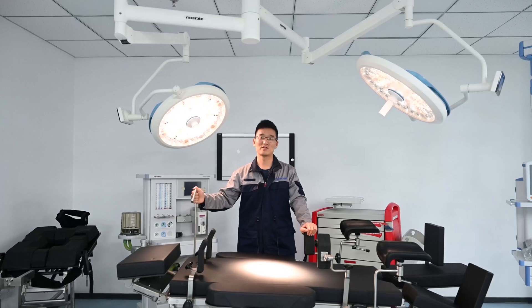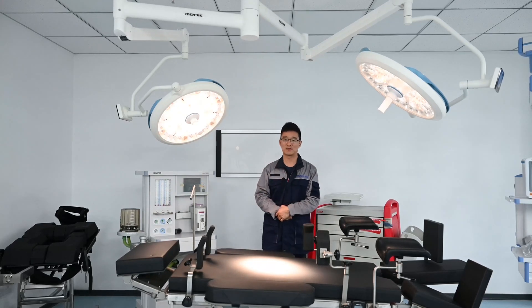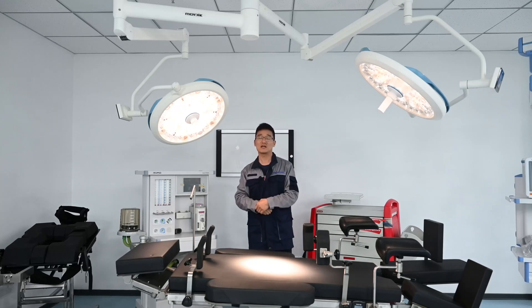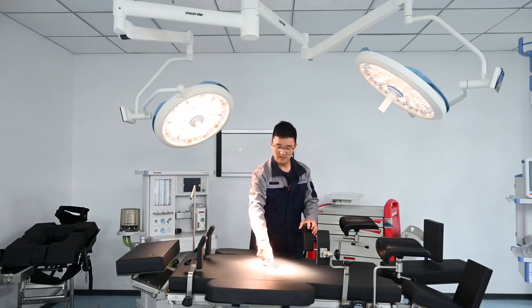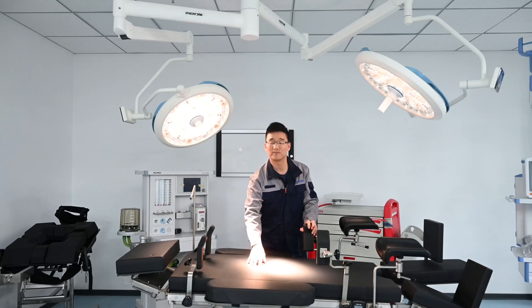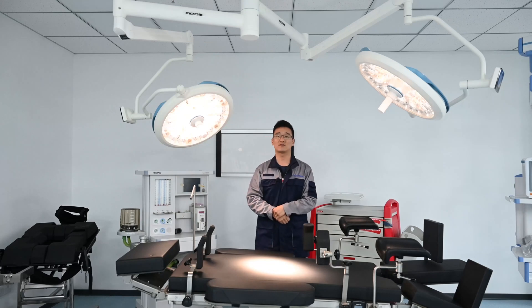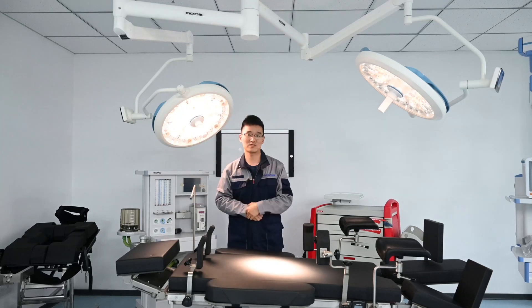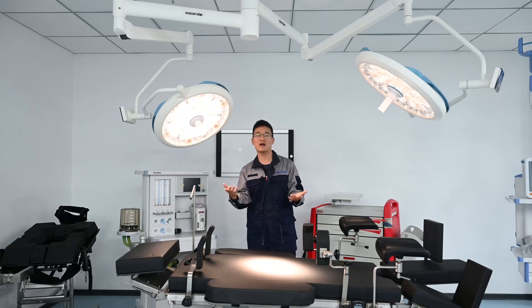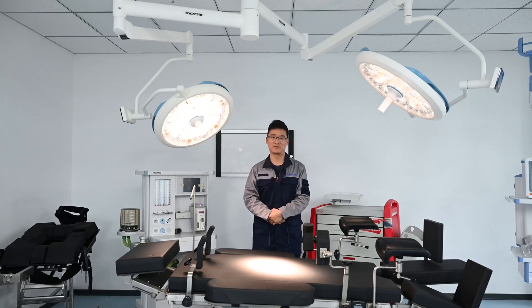To summarize, the good features to consider when ordering or purchasing a surgical light are: first, proper installation; second, a flexible and stable spring arm; third, a bright and even light spot; fourth, a shadowless rate even with obstacles; fifth, slow temperature rise; sixth, light compensation with obstacles if available; and additionally, extra operation modes for laparoscopy or other surgeries are also a good consideration. Thanks for watching.